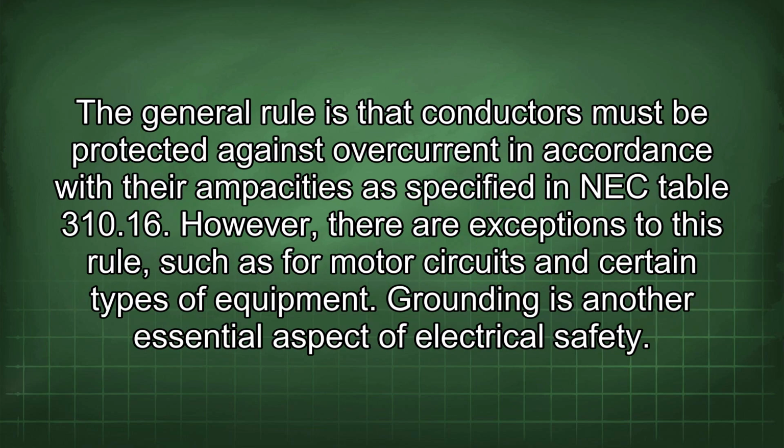The general rule is that conductors must be protected against overcurrent in accordance with their ampacities as specified in NEC Table 310.16. However, there are exceptions to this rule, such as for motor circuits and certain types of equipment. Grounding is another essential aspect of electrical safety.